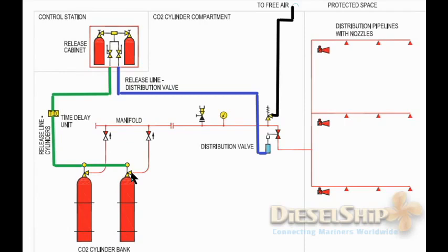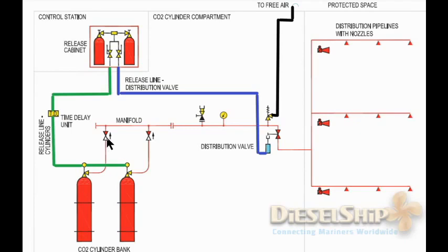As the chief engineer opens the main distribution valve, it has a limit switch which gives an indication that the main distribution valve is opened. After the time delay, the main CO2 bottles corresponding to the engine room are also opened. The CO2 passes through the non-return valve — remember each cylinder outlet has a non-return valve. The CO2 released then reaches the main manifold and through the distribution valve it goes to the engine room, distributed to various nozzles across the platforms.